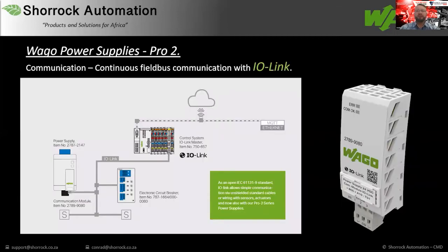In terms of the IOLink, I'd like to show you how we would typically connect the IOLink. And here you can see the IOLink device that clips onto your power supply. We have the IODD file available for your IOLink device. And you can basically then connect this to your IOLink module. And WAGO, like I mentioned earlier on, we have a IOLink module that clips directly onto our controller, or alternatively onto your IOLink module or your IP67 IOLink module, and connect it then to your power supply, pulling all that data from your power supply.